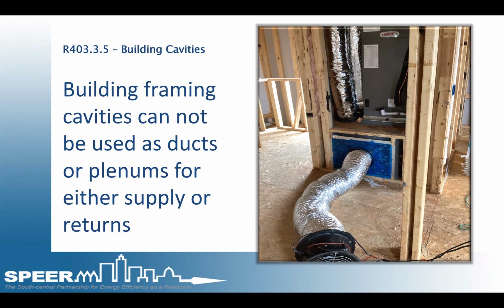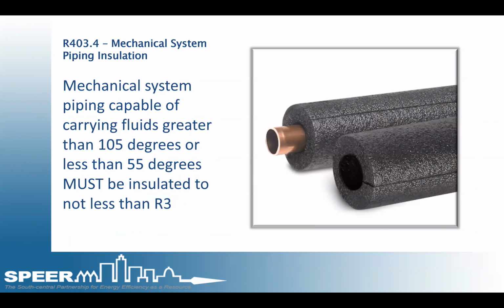These are huge sources of leakage at the time of testing, but even if they get sealed and passed during construction, it will not last for long. The seams and joints will crack and more leakage will occur. This is most likely due to the difference in expansion rates between the wood to wood connection and wood to concrete connection, allowing for leakage. Also, when's the last time you saw these cavities being cleaned out or vacuumed out before the unit is turned on? Usually there's empty cups, leftover lunch, empty tape rolls, and all other kinds of trash that's being left in there. If they're having to put ductboard and sealing all the seams, they'll be cleaning those out and installing the proper ductboard to make that work.